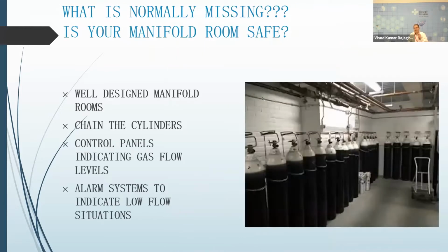Coming to another important area in the hospital, the main manifold room where the cylinders are housed. It should have a proper design because positioning the gas manifolds is important. You have the main manifold, the standby and the emergency manifold. Proper chaining possibilities are needed for the cylinders so they don't fall off and you don't have damage to the cylinders. The cylinders are dangerous when they fall. And the second important thing is to provide control panels which indicate the availability and the volume of gas being utilized, and the control panels should be provided with an alarm system.